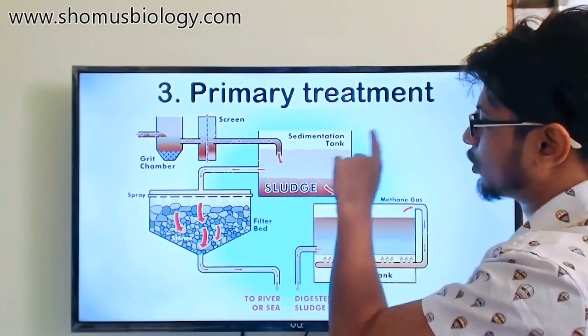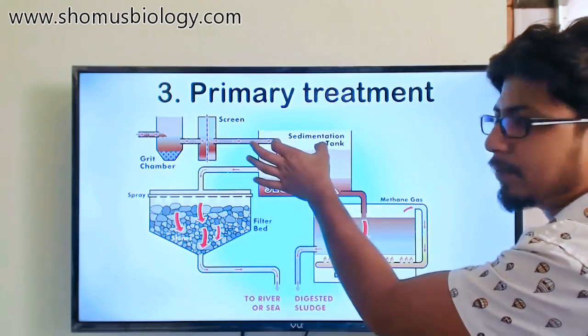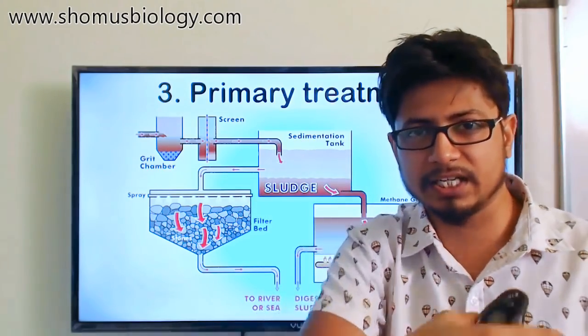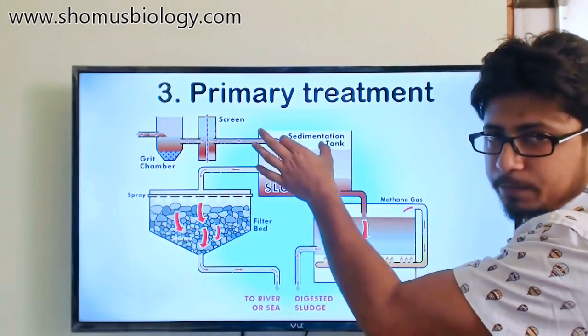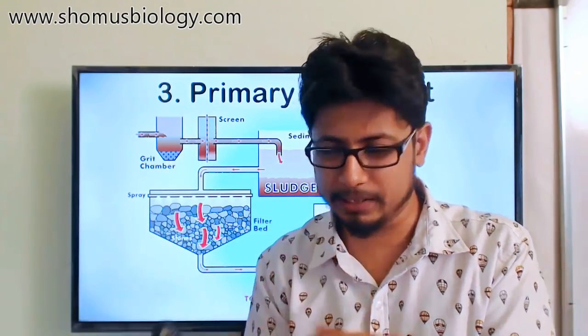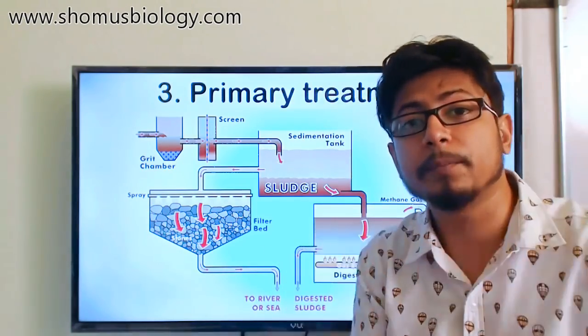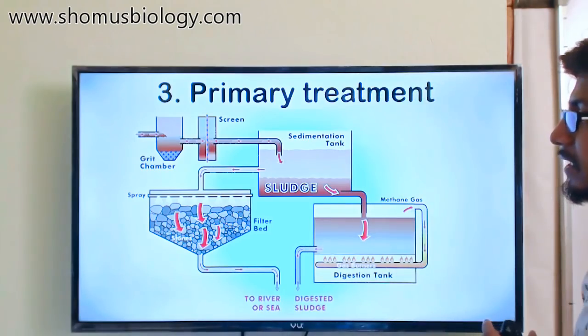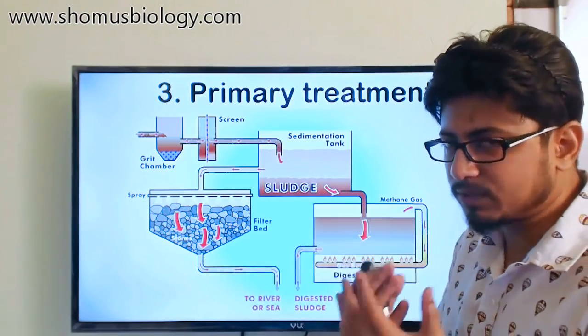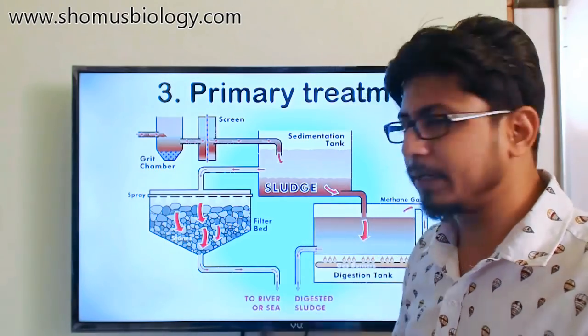In the sedimentation tank there is a rotor with two different arm-like structures — one connecting to the surface of the water on top, and one at the bottom. The bottom arm scrapes all the sludge and collects it at the bottom. The arm on top separates grease and oil-like components, which we call scum. So there are two types of waste produced: scum on top and sludge settled on the bottom.